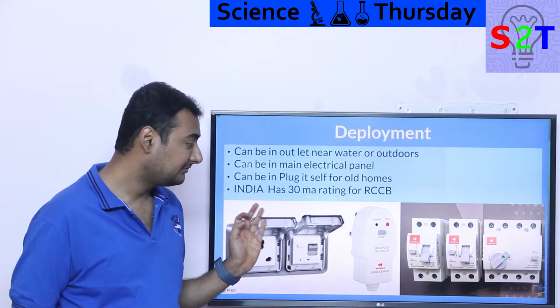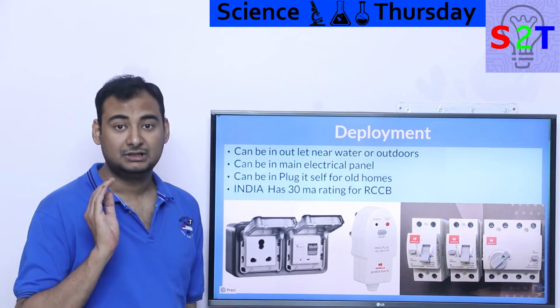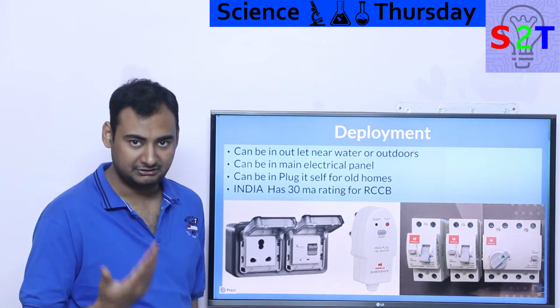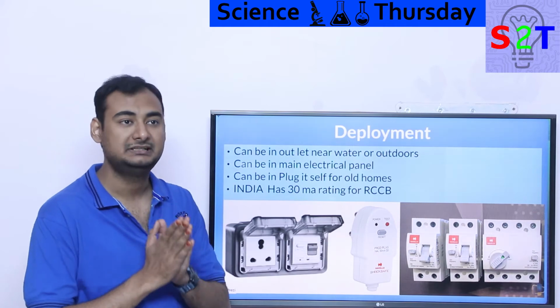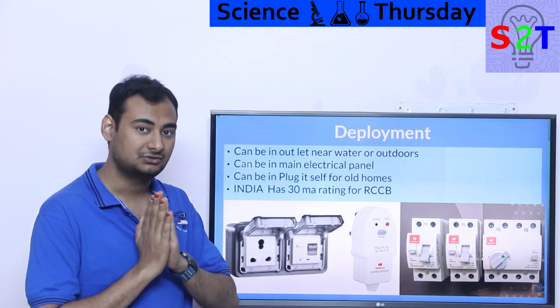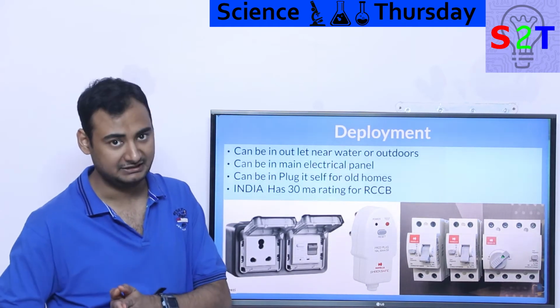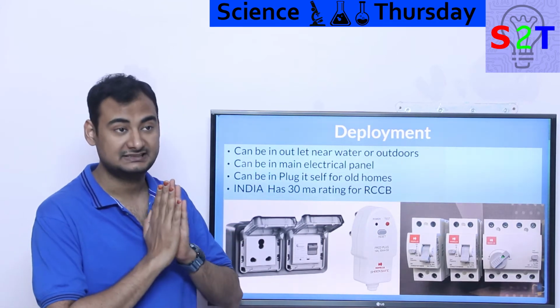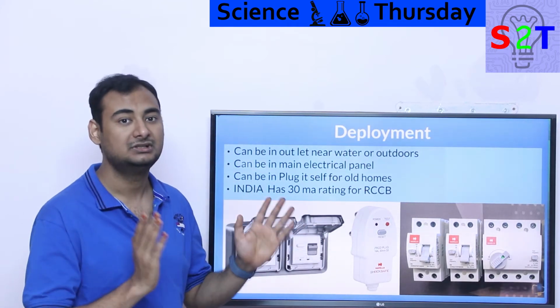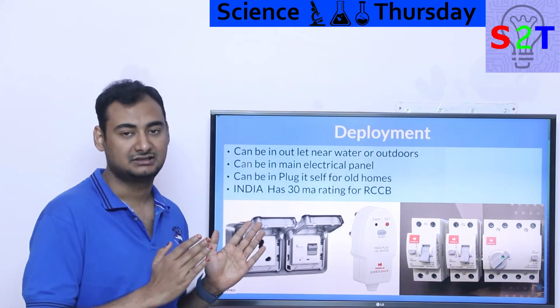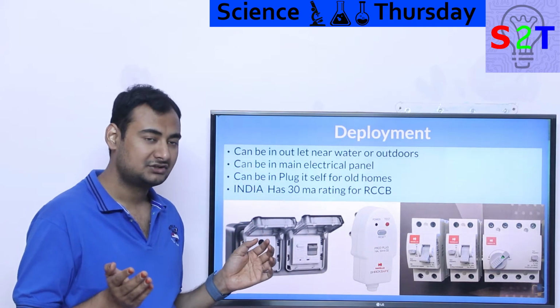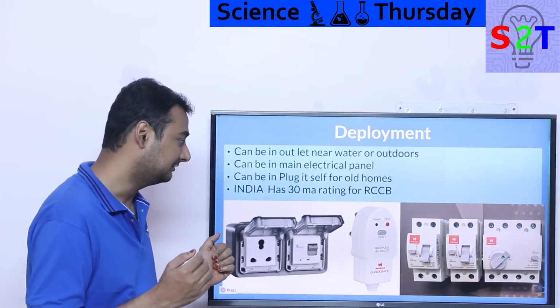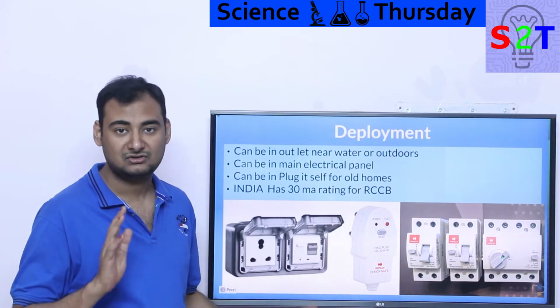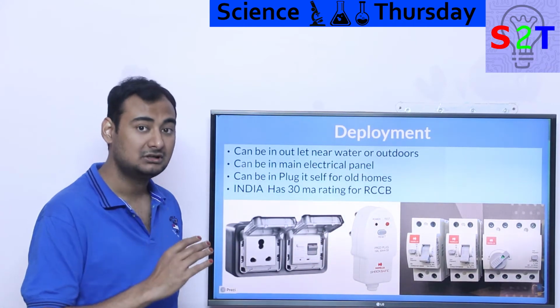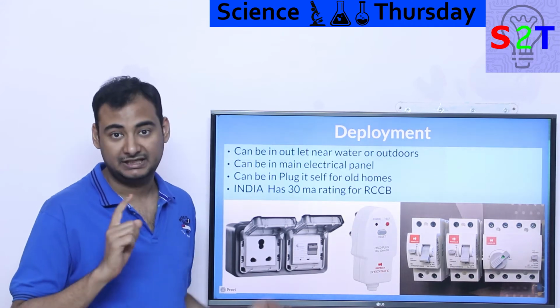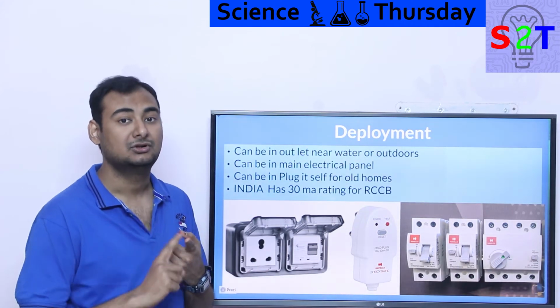Now be mindful, all these things take time to trigger. Generally, during finalization of these devices, the intent is that this puppy should trigger in less than 1/30th of a second. Sometimes it could take longer, but generally that's the requirement. You should disconnect the power in 1/30th of a second. Now why not faster? Because it has an energy limitation. I will explain that further. So be very mindful, these things do not mean that you will never get shocked. It simply means the shock, most likely in most scenarios, A, will not be very painful, B, should not end your life.